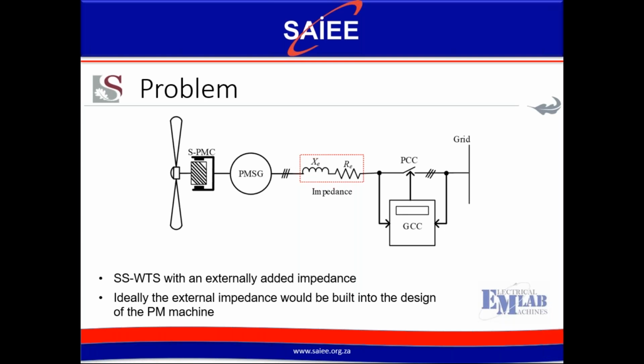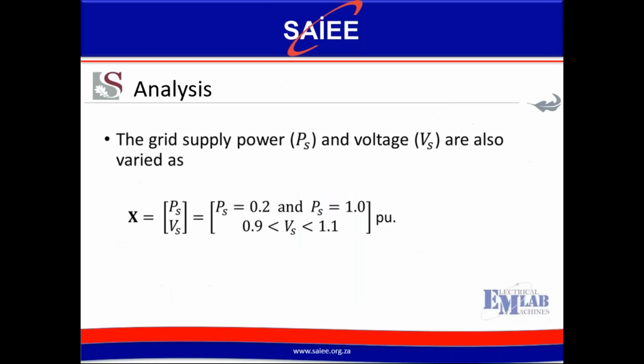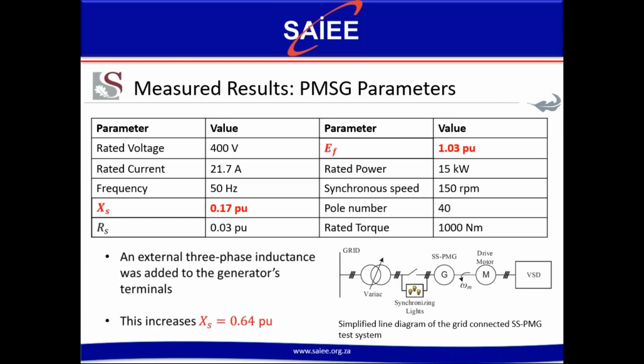In our testing, we just used a 16 millihenry external inductance, and the resistive portion of that inductance was quite low. We couldn't accurately measure it, but during the design optimization of the synchronous generator, which includes this externally added impedance, you'd optimize it to minimize those added losses. That answers the question.